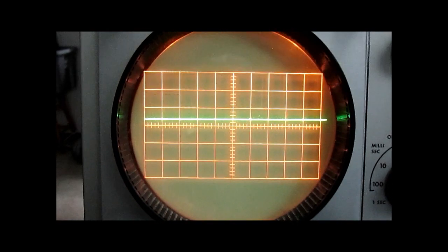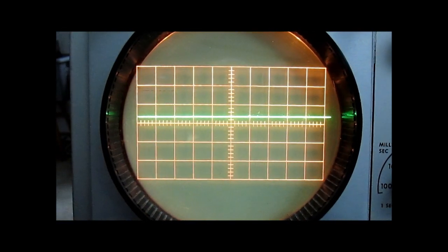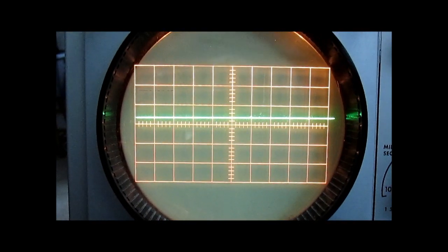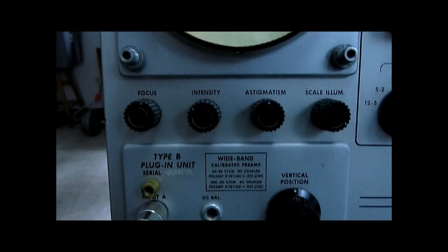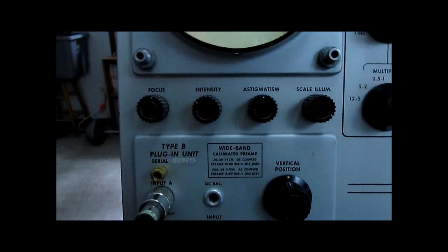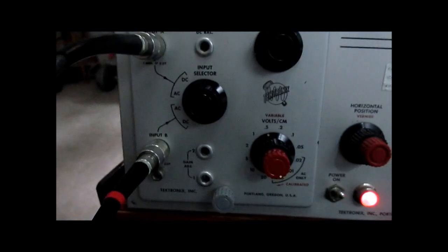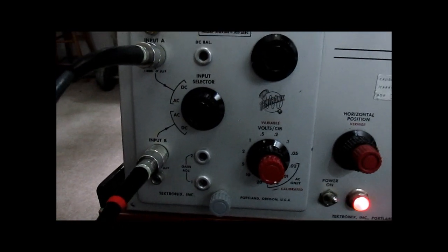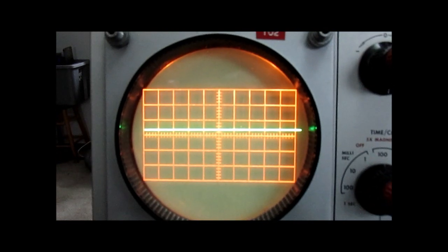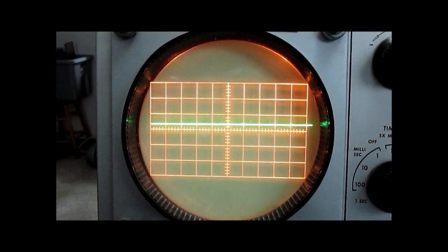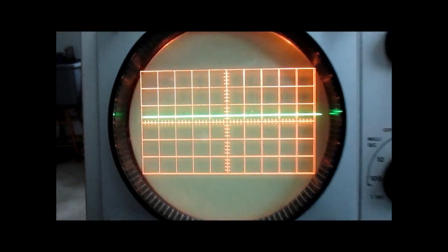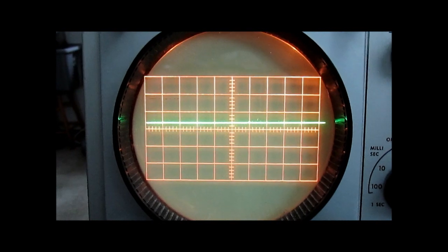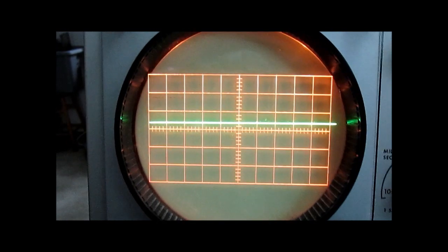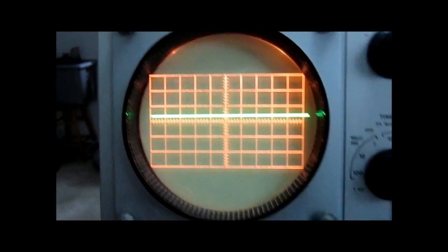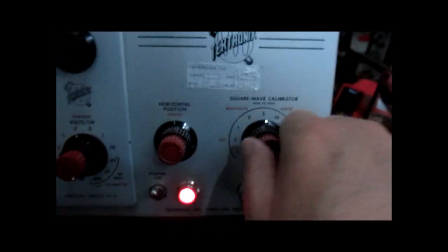So the root cause is probably one of those Black Beauty capacitors inside the plug-in leaking a little bit, and it's changing the bias point on some of the tubes. I've worked on this scope enough and some of the other plugins that I've got that problem corrected when using other plugins. But this one has it, so it's slowly drifting. But it's going to work good enough for this video. Alright, so right now I have the calibrator turned off, so we're going to turn it on.